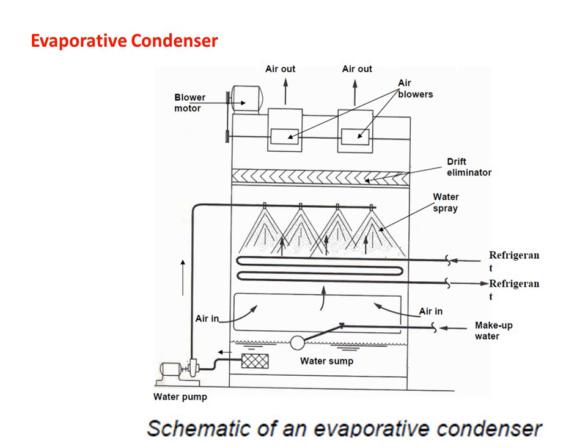The evaporative condenser uses both air and water as the condensing medium to condense the hot vapor refrigerant. These condensers perform the combined function of a water-cooled condenser and a cooling tower. In its operation, water is pumped from the sump — there is a makeup water supply. Air enters from the bottom. This is the refrigerant inlet and this is the refrigerant outlet. Water spray nozzles, a drift eliminator, and air blowers are provided.